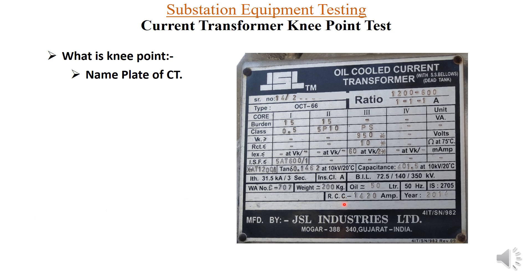Looking at the nameplate detail of this current transformer CT, it has four cores. Vk indicates the knee point voltage, which applies to the special protection core only — in this case, 950 volts. Iex is the excitation current; the value shown is 60 milliamperes at Vk divided by 2, indicating the maximum excitation current allowable up to the knee point voltage.